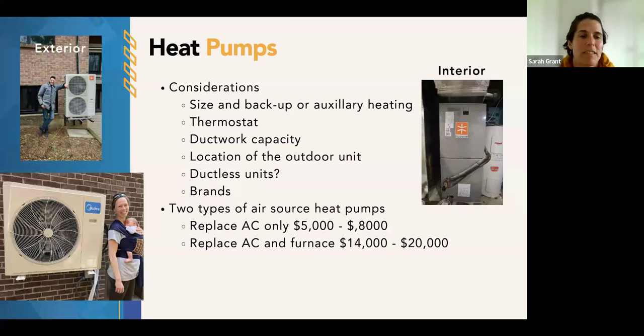On the bottom left is a slightly smaller heat pump that could be wall mounted. If you have a double brick home, you could wall mount yours - ours is wall mounted, which doesn't cause us any noise issues. For some framed houses, I don't recommend it, and double fan units I don't recommend wall mounting either, since the vibrations are too much and you'll get noise coming through the house. But in a small house where you don't need a large heat pump, wall mounting is a good option. I should have grabbed pictures, but some homeowners have done nice lattice work around their units to help blend them into the garden.